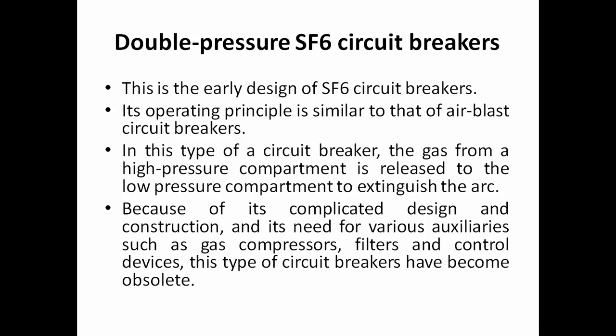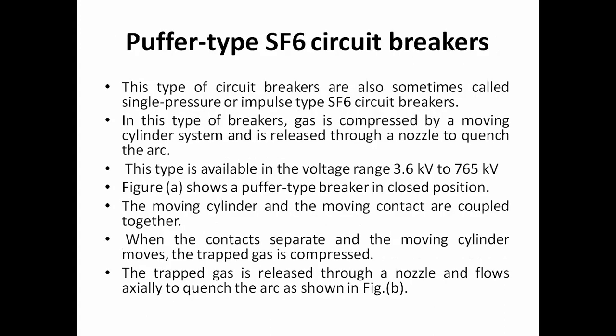But again, in the case of the double pressure SF6 circuit breaker, in low temperature areas we generally require thermostatically controlled heaters, and we require compressor units to flow the compressed gas. So in that case, these types of circuit breakers can be obsolete in today's scenario. In order to overcome these disadvantages, we come to the puffer type SF6 circuit breaker.